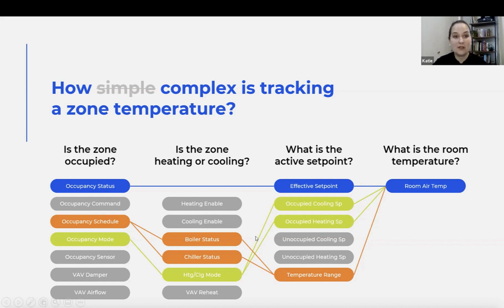And then you'd need to know in some cases whether your zone is in heating or cooling. It's not always the same point that you're looking at in the BAS system to determine that. And then what is your actual set point? Sometimes you have ranges, sometimes you have an occupied heating and an occupied cooling set point, and sometimes you have the really easy effective set point, but not always. And so when you start to copy and paste that, each time you're putting it on a new zone, you're customizing it. And then it becomes very difficult to maintain and to keep it going.